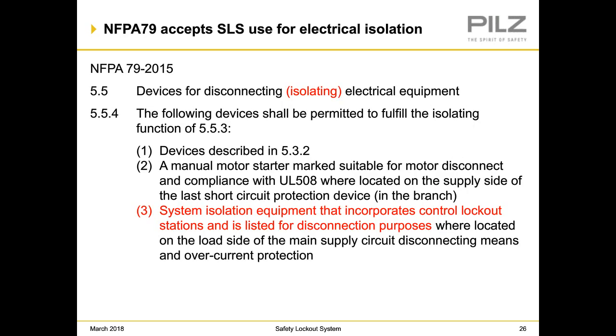NFPA 79, also devices for disconnecting isolating equipment. And if you look at the third one down there under 5.5.4, system isolation equipment that incorporates control lockout stations and is listed for disconnection purposes. And again, we're located on the load side. These are always located on the load side of the main supply, as well as the overcurrent protection. So they're located after the main supply and the overcurrent protection.